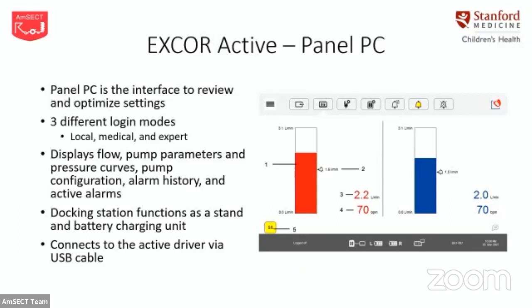except for the manual versus automatic pressure control. And then logging in as expert, you have access to all of the functions. You also can silence alarms for 30 minutes when you're logged in as expert. That's what we as perfusionists typically log in as when we're doing initiations, explants, pump replacements, things like that.